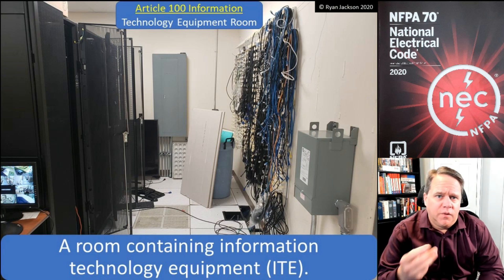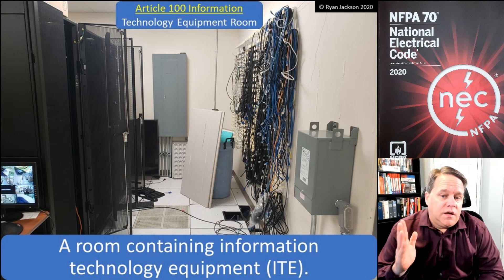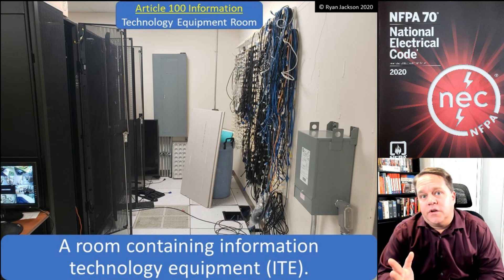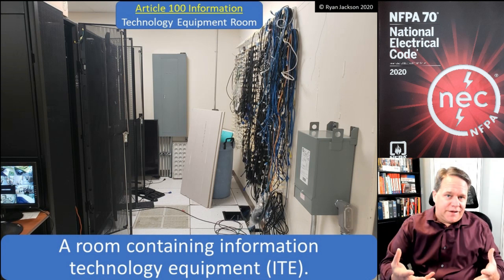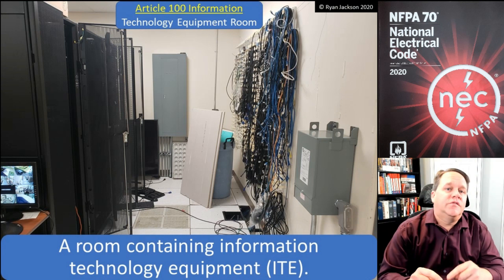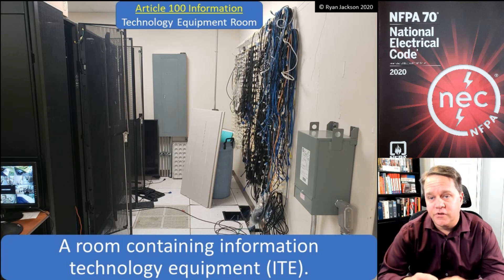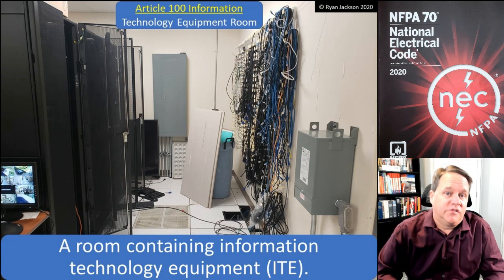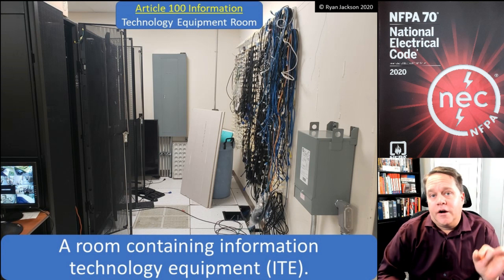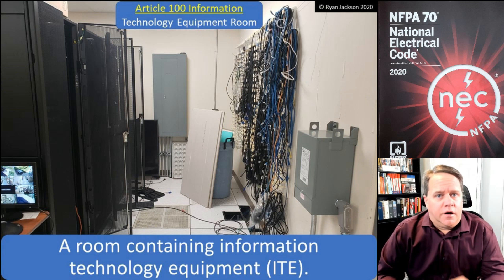They had to figure out a way to accommodate IT rooms, and what they ended up doing is creating Article 645. The crux of 645 is that back in the day you really couldn't use plenum rated cables in some IT equipment rooms. We need plenum rated cables in air handling spaces in case there's a fire, because the smoke from non-plenum rated cables is very toxic and we don't want it traveling through the building's air handling system and killing people.